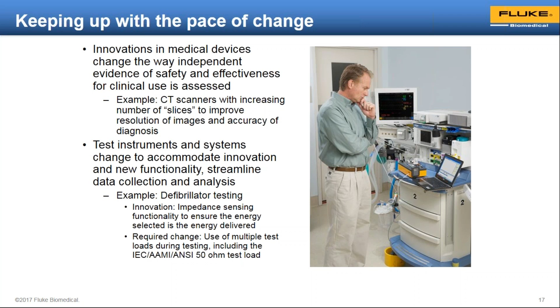If you don't have the ability to test that functionality by delivering several different impedances when you're doing your testing, you are not fully testing that medical device. And if that device fails, you will have a much bigger problem, including litigation. So it's really critical that we do this job well and that we do it right, and we think it all the way through on the process.